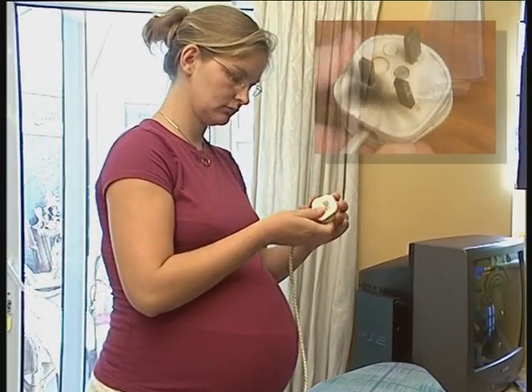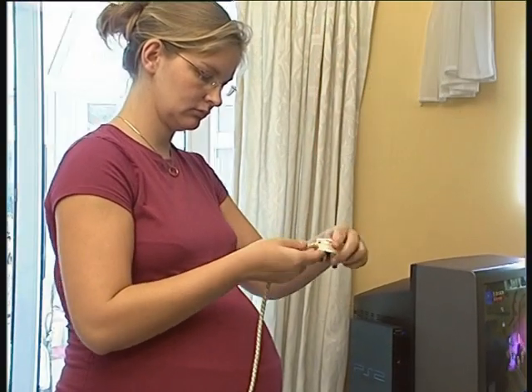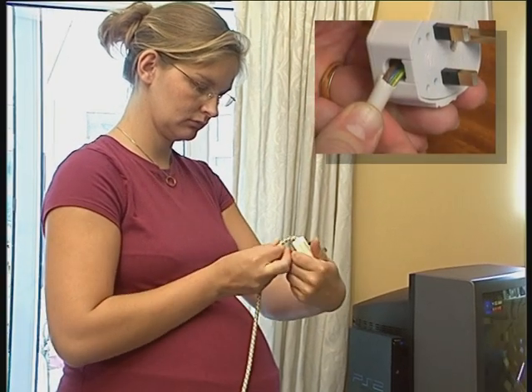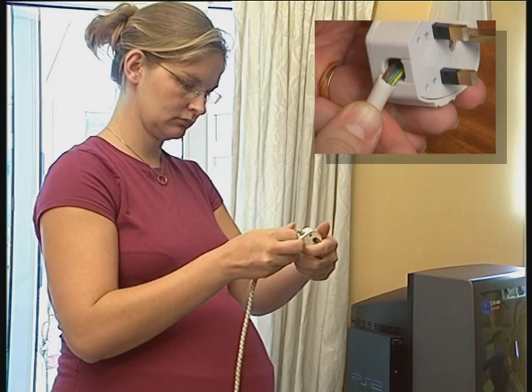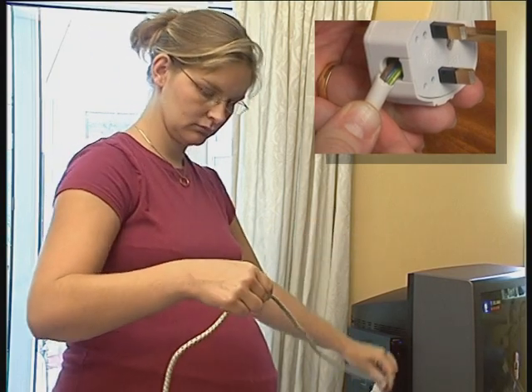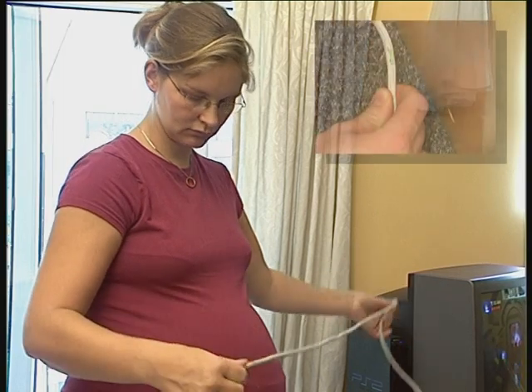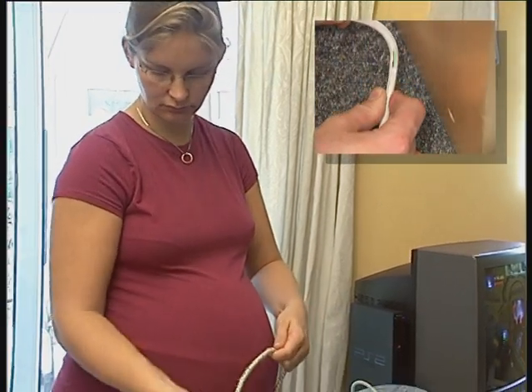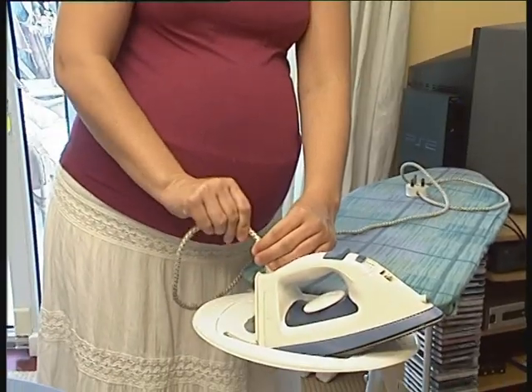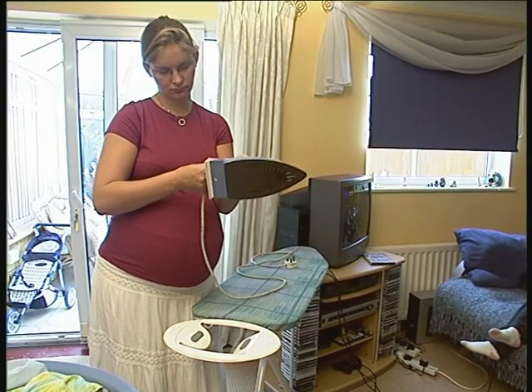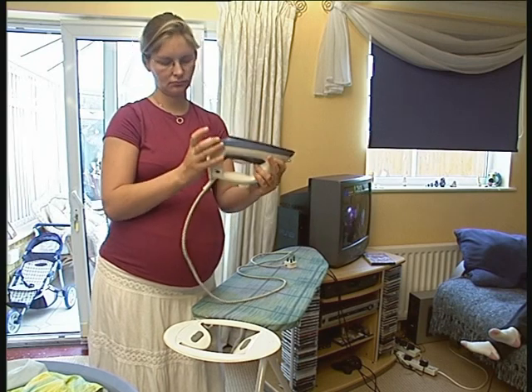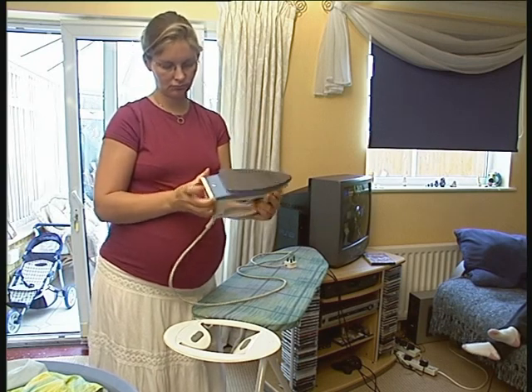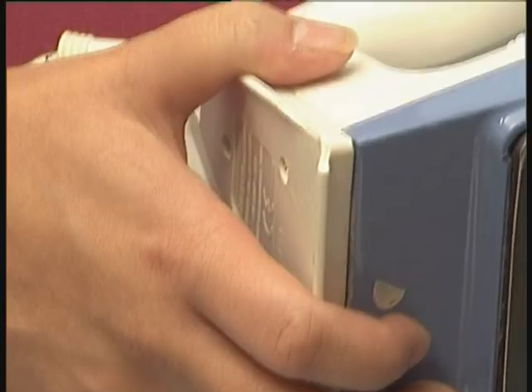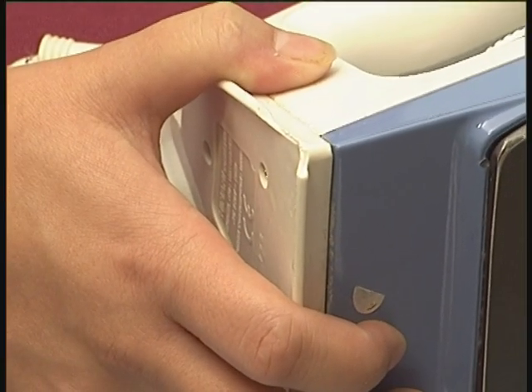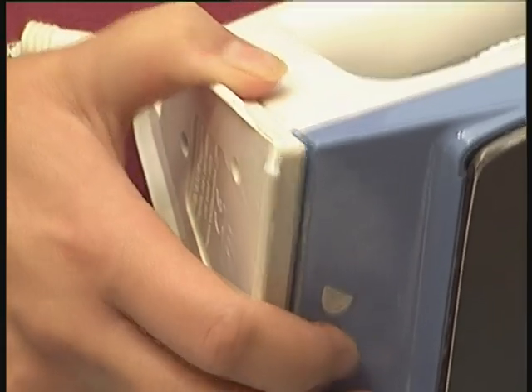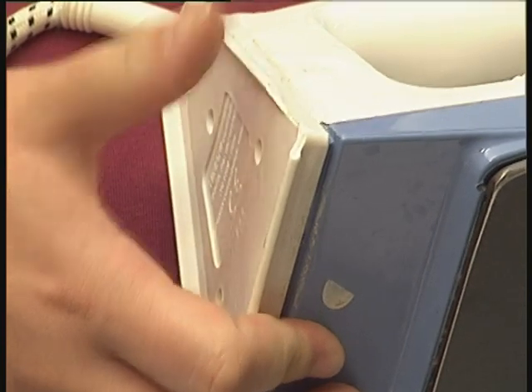Start at the plug, looking for cracks or signs of electrical burns. Is the lead secured firmly into the rear of the plug, with no exposed internal blue and brown wires showing? Or worse still, bare copper conductors? Then check along the supply lead, looking for signs of wear or damage to the plastic sheathing. Finally, check the appliance itself. Does the flex enter the casing without the inner cores being exposed? Is the flex properly fixed to the appliance? Is the casing free from damage and any signs of electrical overheating? If you suspect that anything is not as it should be, do not use the appliance.